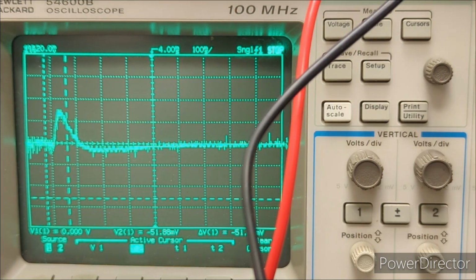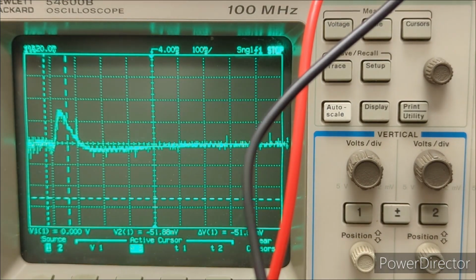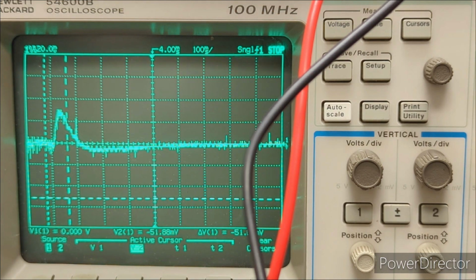Okay, so again, I'm not going to do the measurement because we'll just use divisions, but you can see, looking at 20, not even 40 millivolts. So again, it looks like it's within spec. This is definitely going to be the max output of this supply at 240 watts. So it's looking good.